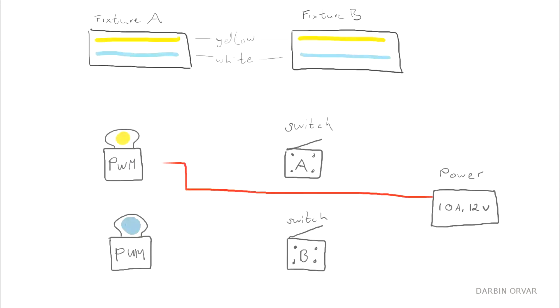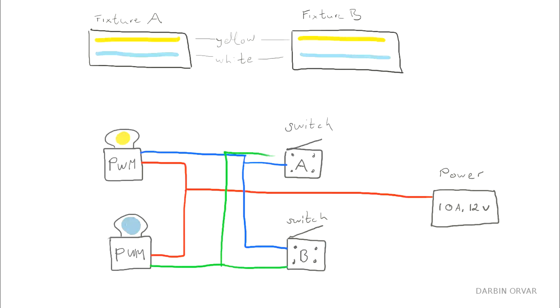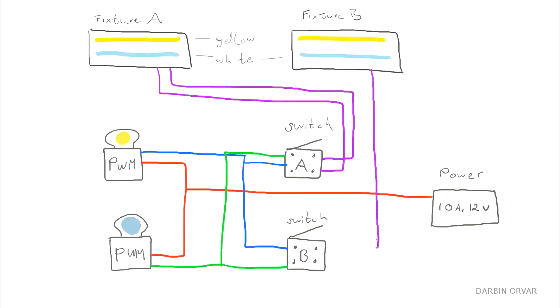The complicated part here is the dimmers each affect the colors of the lights, but the switches control the fixtures. So that means you have to independently switch the colors to each fixture. And that requires a switch that can switch more than one line independently.